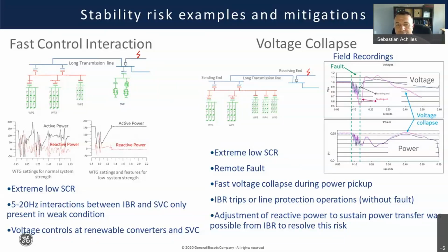So you get a fault. As a result of the fault, the voltage drops on the sending end. The wind turbines see that, and it's very common in the industry that if the voltage magnitude is reduced, the IBRs will tend to reduce the active power. The voltage magnitude is used as an indication that the system cannot really take the full power. So you reduce the power out of the IBRs, and that's what you see on the second marker. At the time of fault clearing, the active power being injected by the IBR is noticeably lower than before the fault.